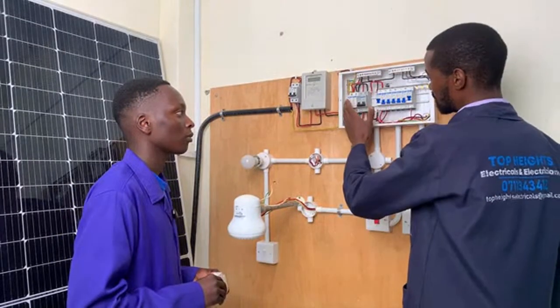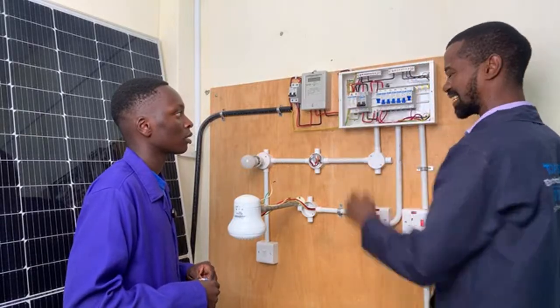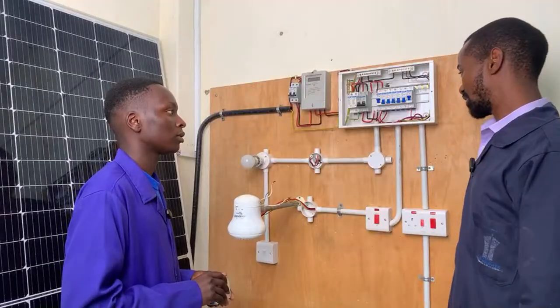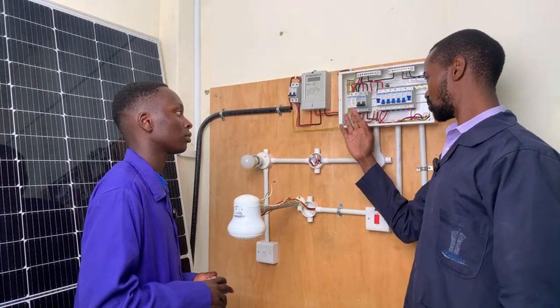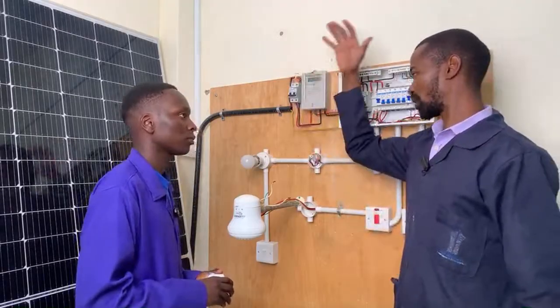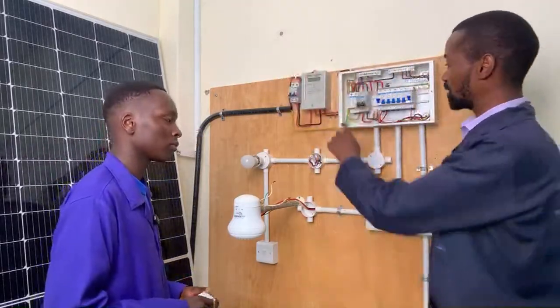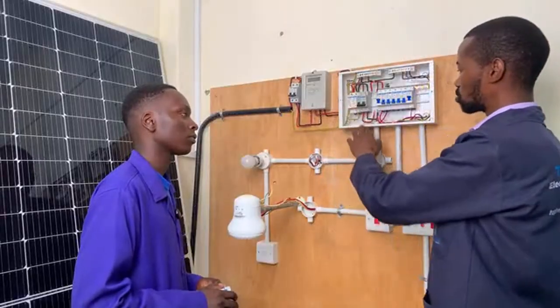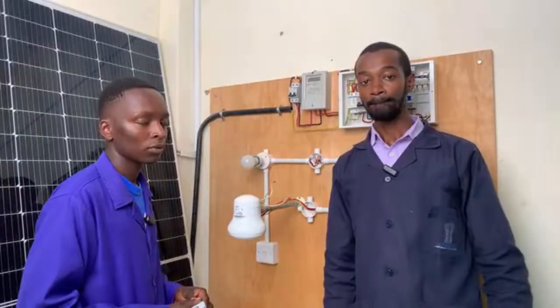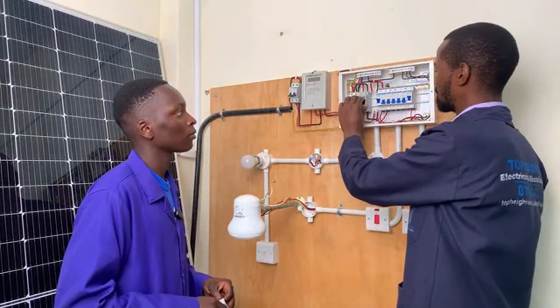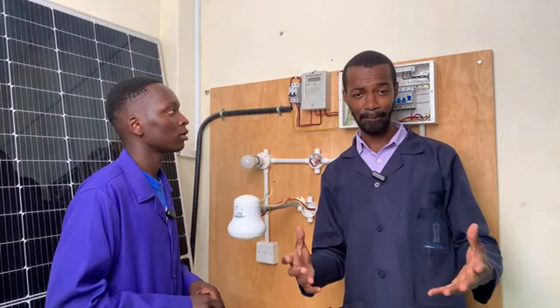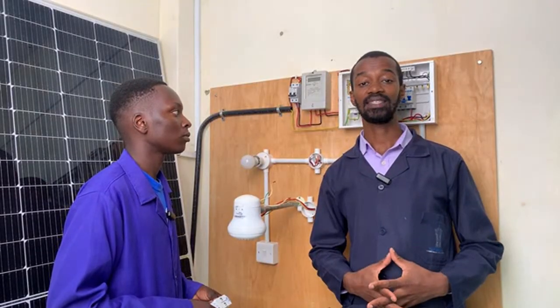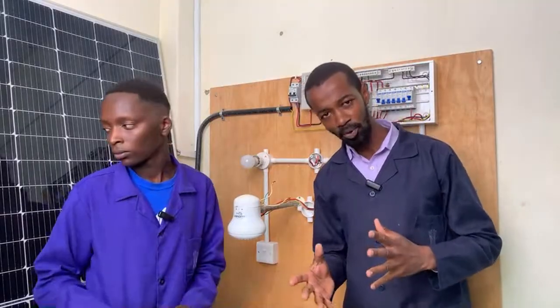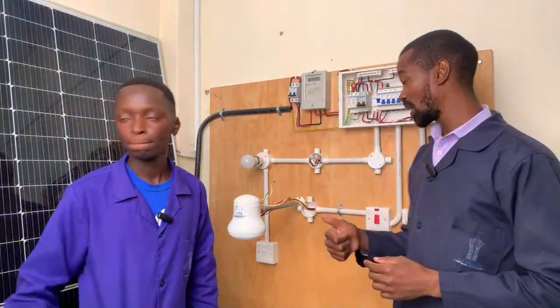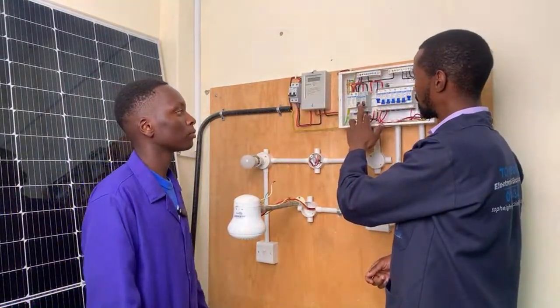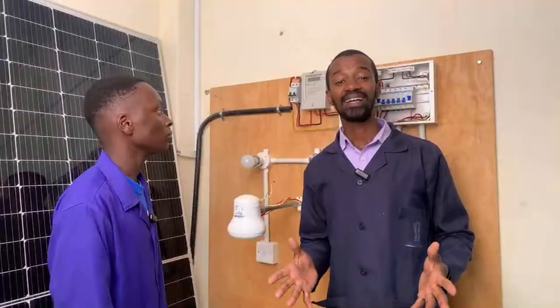In our consumer unit, for instance, what we have here is a surge diverter. The good thing about the surge diverter is that here in our country, we have a lot of faults coming all the way from the national grid, and that will definitely strike the customer. That is why in my consumer unit, I have that SPD. Number two, we definitely have this, which we normally refer to as a DPMCB, double pole miniature circuit breaker. Other people can also refer to it as a main switch, which in other countries is called an isolator.